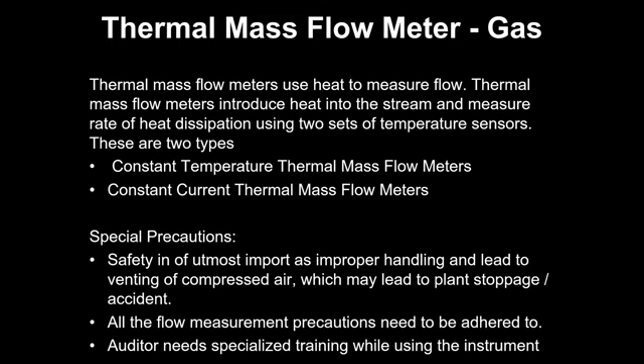Now the working principle is similar to what we talked about for the anemometer, but it is a more sophisticated, more expensive thing. So they'll have two probes. One will measure the temperature. Another will emit a current, either constant current or varying current and constant temperature. And based on that, we'll measure the m Cp delta T, which will tell you what is the flow rate. So this is the working principle.